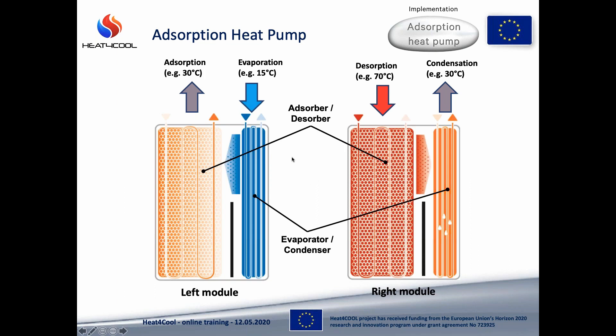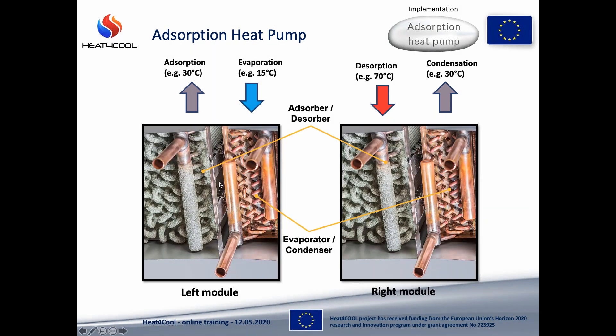To keep this process continuous we have to have at least two such modules working out of phase. When in one module the sorbent is absorbing water, in the second module the sorbent is being regenerated. In the real machine we have two fin-and-tube heat exchangers — one, typically the bigger one, is coated with sorbent (in this case silica gel) and the second one is not coated. The heat transfer fluid HTF flows inside the tubes.